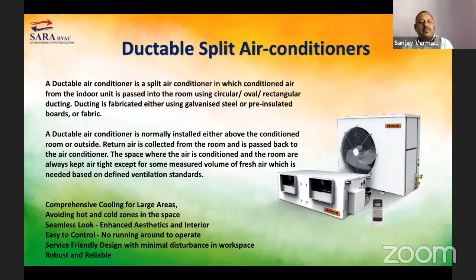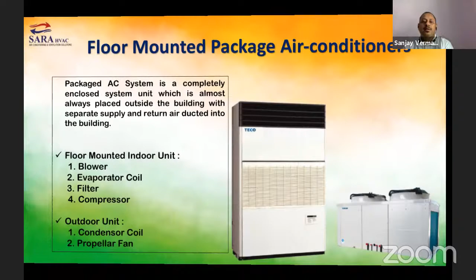The next type is floor mounted package air conditioners. The package AC system is a completely enclosed system, almost always placed outside the building, with separate supply and return air ducted into the building. The big photo shown here is the floor mounted package AC, kept in a closed room with the duct mounted from the top. We run the duct into our conditioned area, while the condenser unit is kept outside the room. The indoor floor unit consists of blower, evaporator coil, filter and compressor, while the outdoor unit has just the condenser coil and propeller fan.